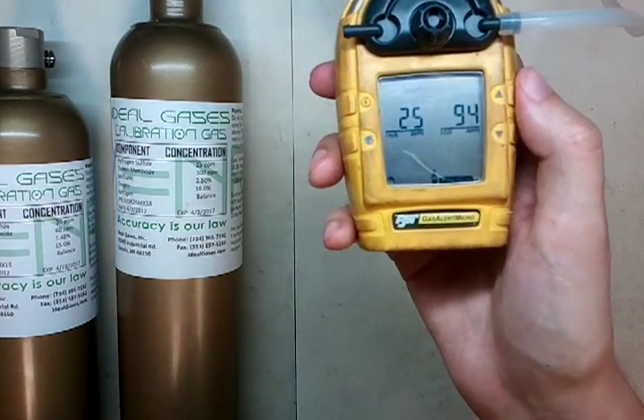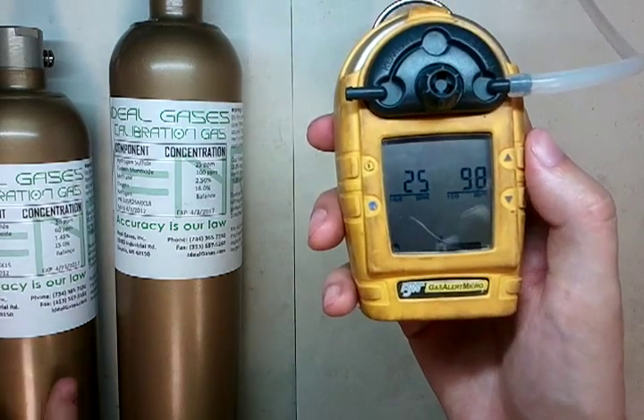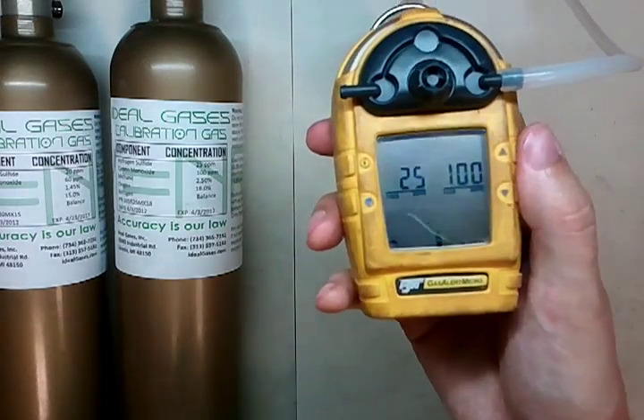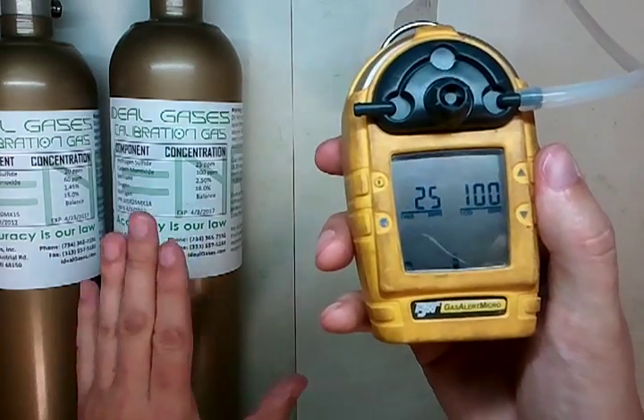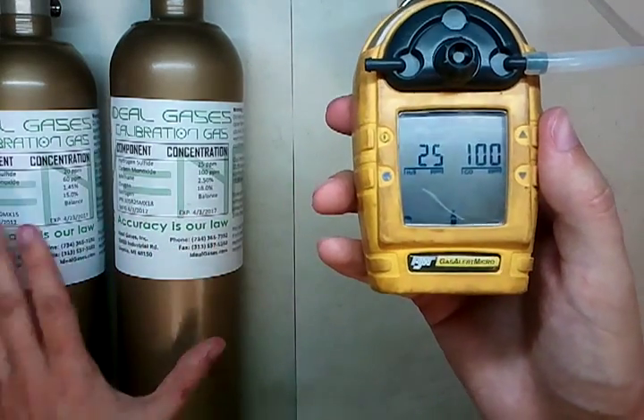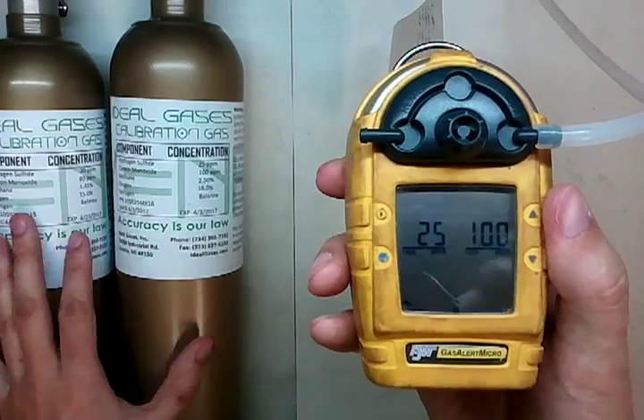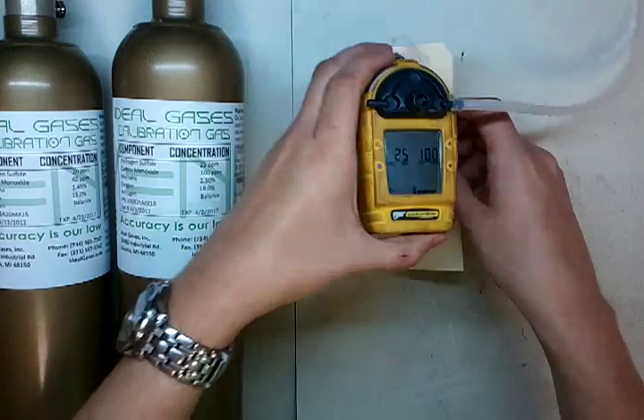Now, you've done everything you can — you've bought this new sensor. You might think the only thing left is sending it to Honeywell saying we don't know what's wrong, or is it a board error? Well, it's not a board error — it's a software error. But there's no way to fix it through the monitor settings; you can't tell it to reset to how it came from the factory. I'm going to show you guys a quick trick on how to fix it — or you can send it to us and we can fix it for the cost of about two calibrations.